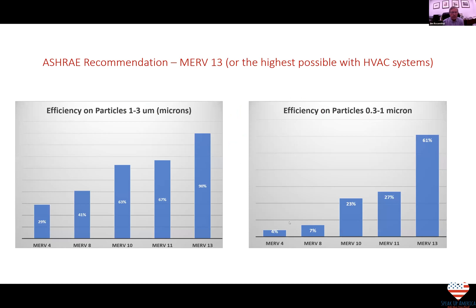ASHRAE's recommendation is for MERV 13 filters, or the highest possible compatible with HVAC systems. Looking at two charts — one showing efficiency on particles one to three microns, the other on particles 0.3 to one micron — MERV 13 filters in both categories are substantially better than other filters. That's why the recommendation is what it is.